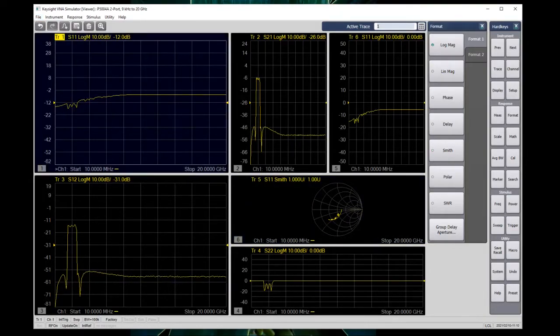Okay, there are a few things that you can't do, especially without the hardware. One of them is calibrations. When you see all this grayed out stuff, it means that you can't make any changes on that. It makes sense, right? You need a different eCal. A different cal set has different performance. We can't just simulate the default things.